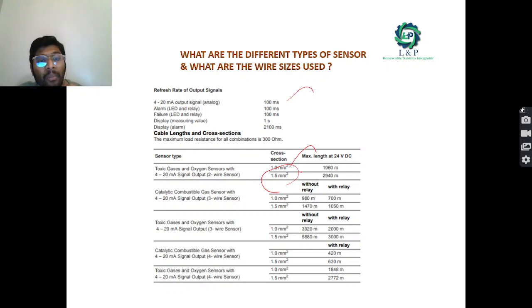And what is the maximum length you can use if you are going to detect with the oxygen sensors? For the 24 volt DC connection, the maximum for 1 square mm is 1960 meters, and for 1.5 square mm, you can go up to 2940 meters.